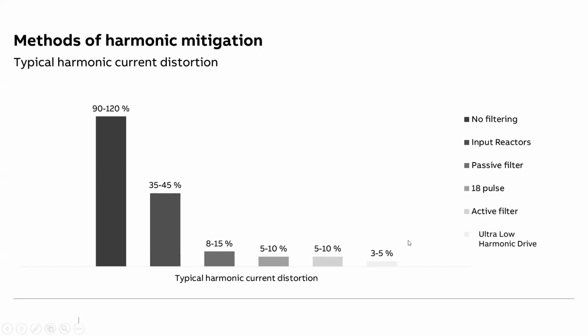So then a premium solution which is available is the ultra low harmonic drive or an active front end technology. So this 18 pulse is also a technology which is available. However, it is not applicable to us. This technology is not used in HVAC systems. This is only suitable for industrial applications where big drives are used.